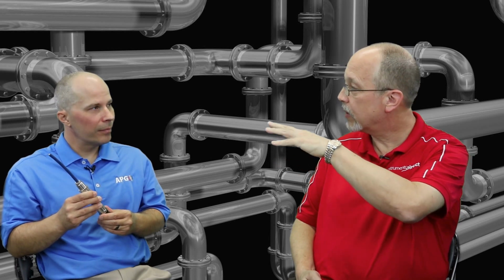Yes, that can happen. Now what about applications that you have, say chemical applications? Don't you have material compatibility issues then? What do you do? Yeah, absolutely, these are really good from a chemical standpoint because you've got Delrin for the cap here, you've got 316L, and then you got three choices for the cable: PVC, polyurethane, and Hytrel. Usually for a lot of the aggressive ones, people will choose Hytrel, but you'll have to check to see if it works for your application.